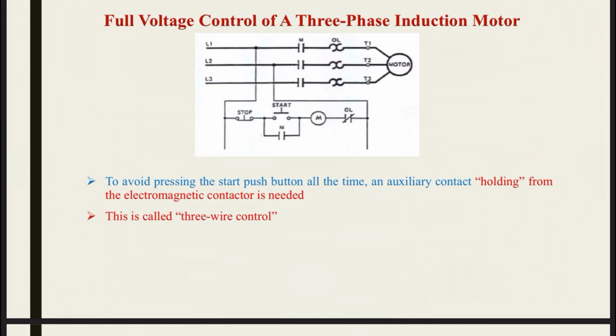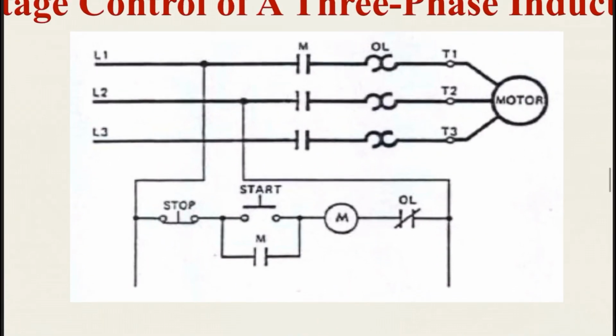Now, to avoid pressing the start push button all the time, an auxiliary contact named holding contact from the electromagnetic contactor is needed. This is called three-wire control. Now we will add, and we can zoom in, a normally open contact from the main coil here, to keep the start push button depressed, to keep the pressing of the start push button.